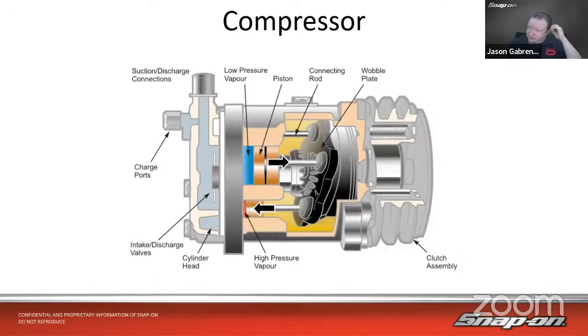Probably the more common one is going to be one with a plate. So we have either a wobble plate style or a swash plate style. You see we have the charging ports, intake and discharge valves, the cylinder head here, and these pistons that float around on this plate that wobbles. As it does, it acts like a crankshaft. If you're thinking about a straight line engine, it does the same type of thing. It just wobbles around and pushes it in and out. We actually have an animation here in a minute.